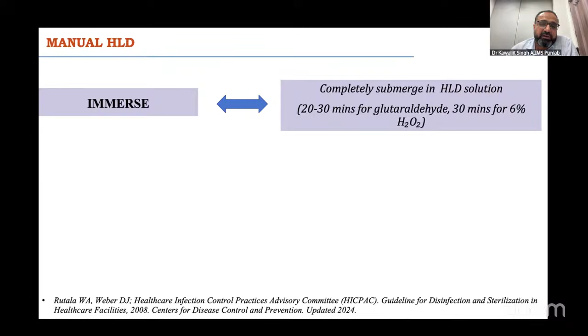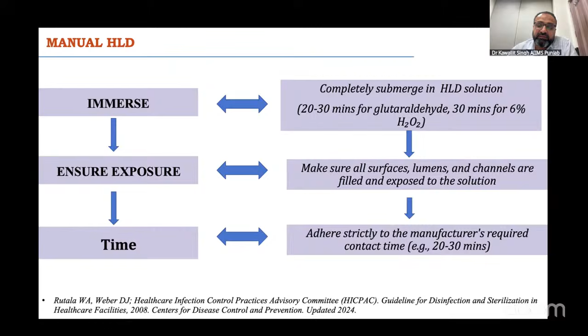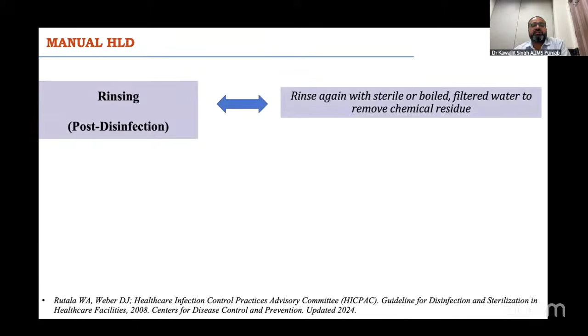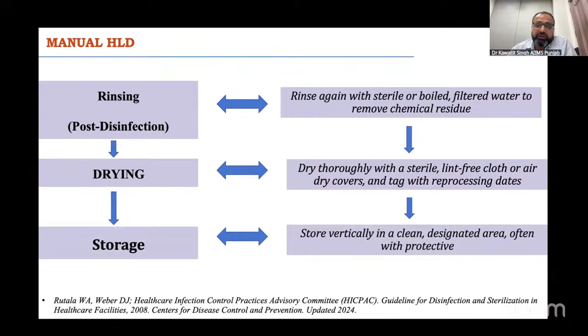We have to ensure that there is proper exposure of the scopes or the instruments to the chemical. Make sure all surfaces, lumens, and channels are filled and exposed to the solution, and adequately and strictly adhere to the time duration as given by the manufacturer company. Then followed by post disinfection rinsing with sterile or boiled water, filtered water, to remove the chemical residue. This needs to be followed by drying. Drying thoroughly requires a sterile cloth or air dry cover, or we can completely dry it, followed by the storage. Store vertically in a clean designated area, often with protective covers.